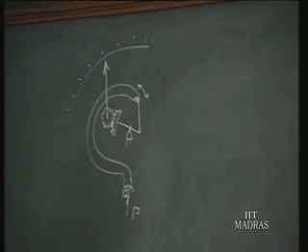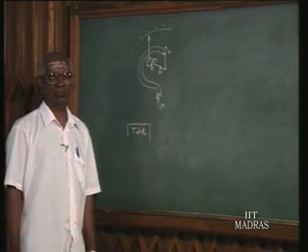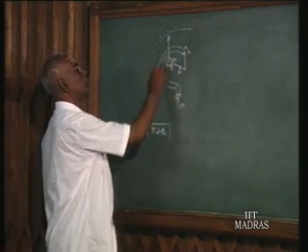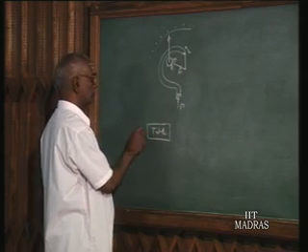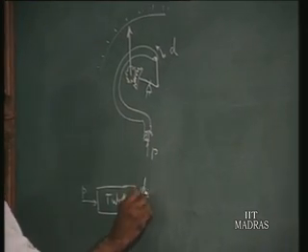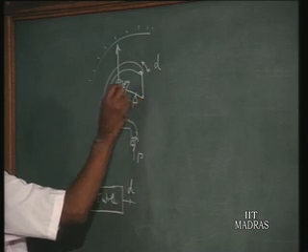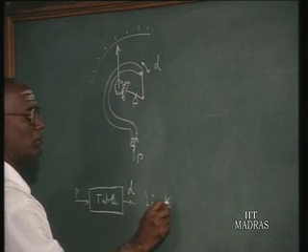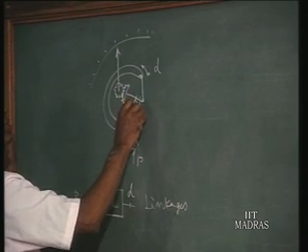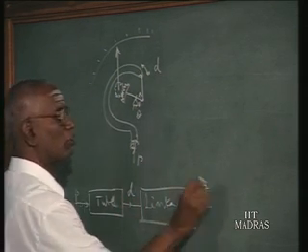Now, what is the signal? So to say, signal flow diagram. The signal flow diagram helps us to understand how the instrument is functioning. For example, now the tube transduces the pressure into a deformation or deflection D. And this displacement D is taken up by the linkages. So linkages convert it into an angular rotation theta. So here you have got theta. D is converted into angular rotation theta.